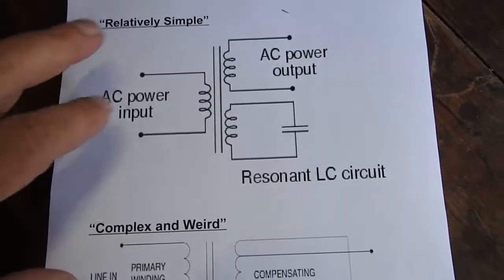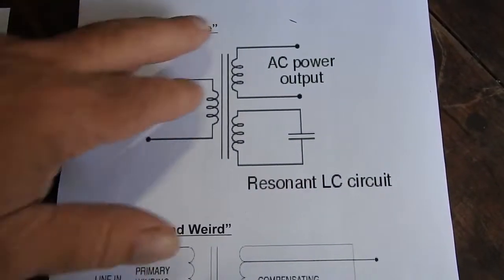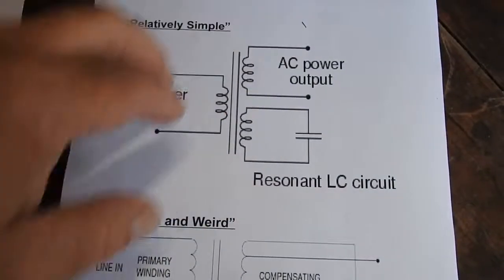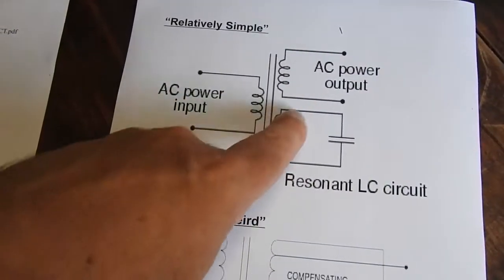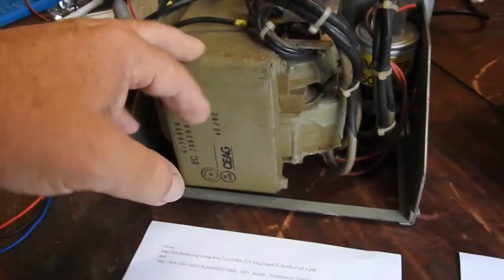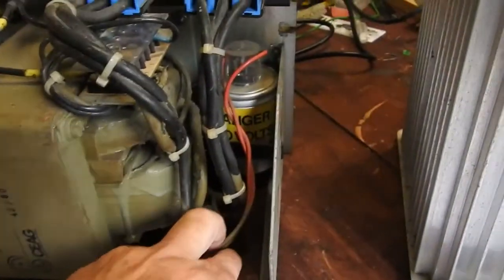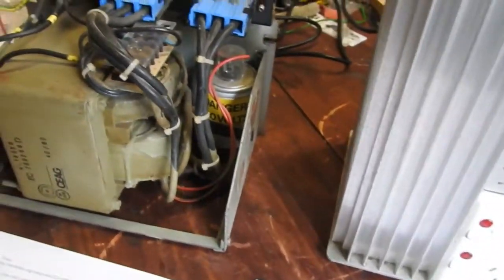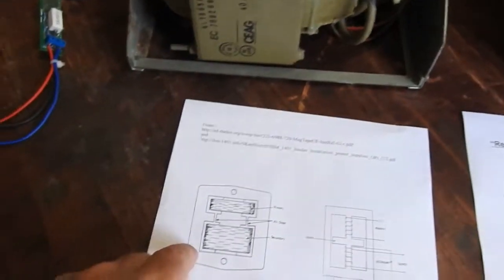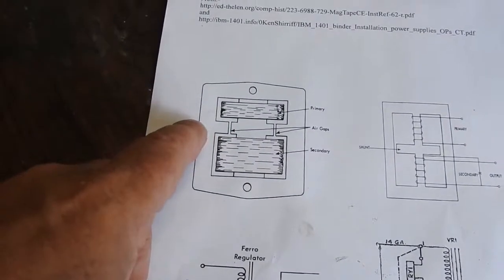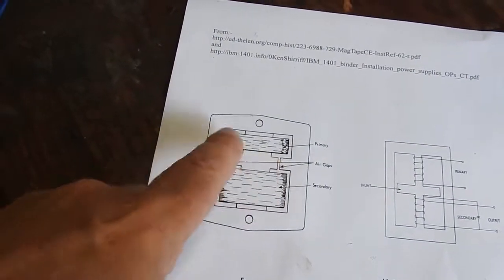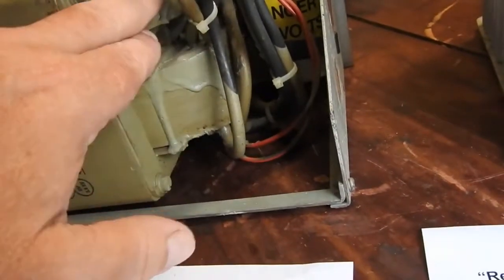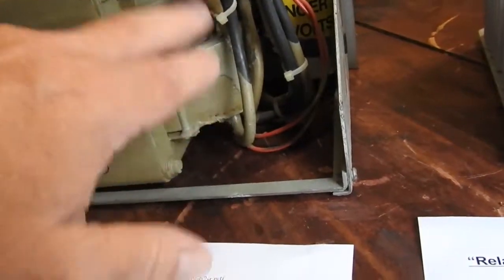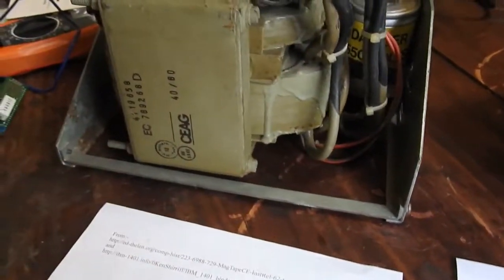Relatively simple looks like an ordinary transformer, a primary and a secondary, but with a third winding with a capacitor in parallel to it. What's not so obvious is that mechanically, the primaries and secondaries are always wound separately, not together on the core, they're physically separated.